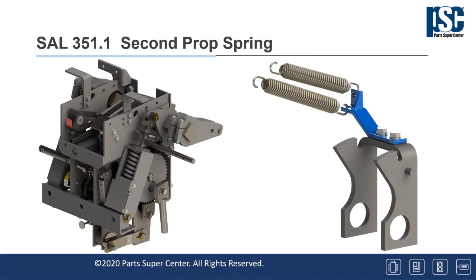Next is SAL 351.1, which adds a second prop retrieving spring to return and reset the prop on the ML13 mechanism during a breaker closing operation. Operating experience in the late 90s showed random failures to latch. After investigation, it was determined that inconsistent prop action was the root cause. The addition of a second prop spring allowed for consistent and earliest reset of the prop under the prop pin with minimal rebound and over travel.